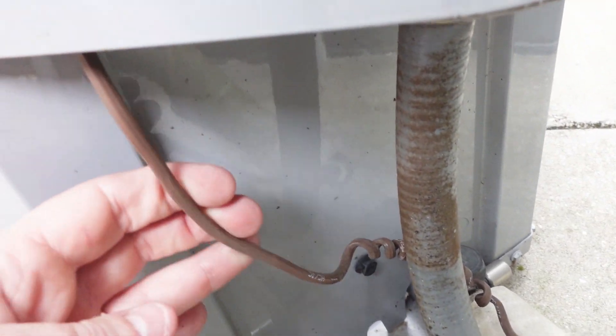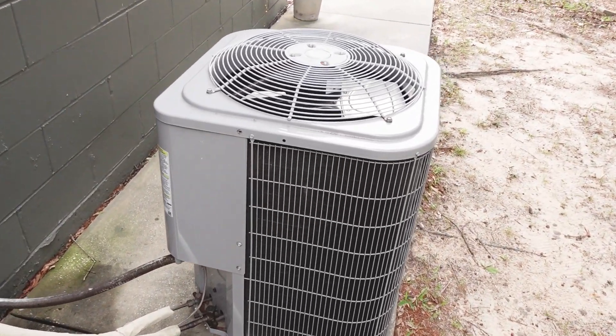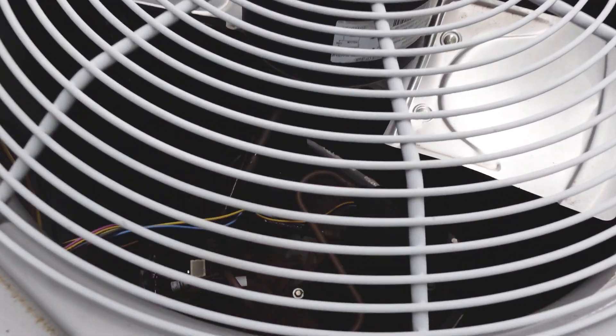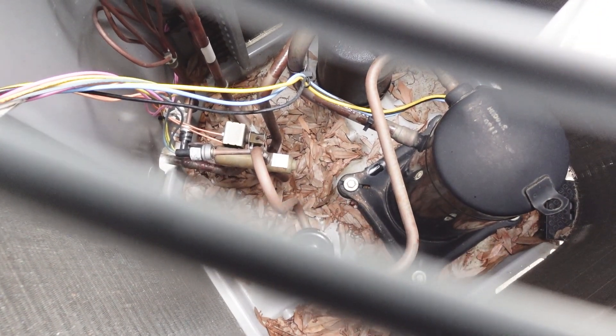Inspect your control conductors outside. Ensure that there's no damage from weed eaters or other lawn equipment. Look inside of your condensing unit and ensure that none of the conductors inside are rubbing against any of the copper tubing, causing chafing and damage, which can often lead to a low voltage fuse short.